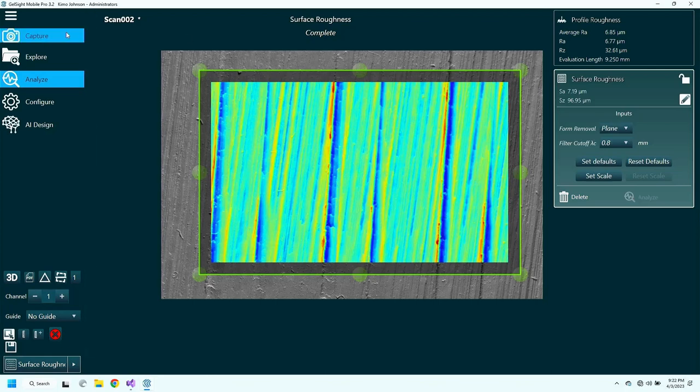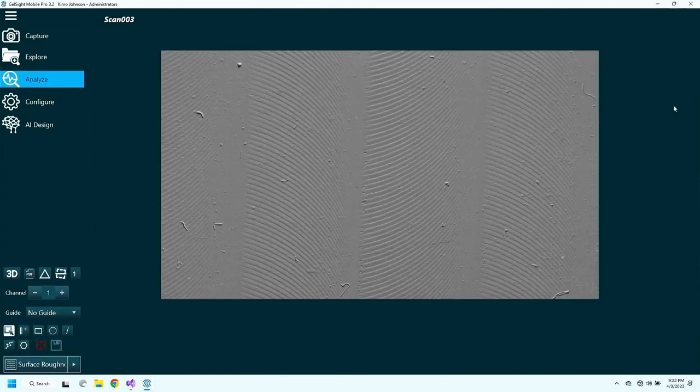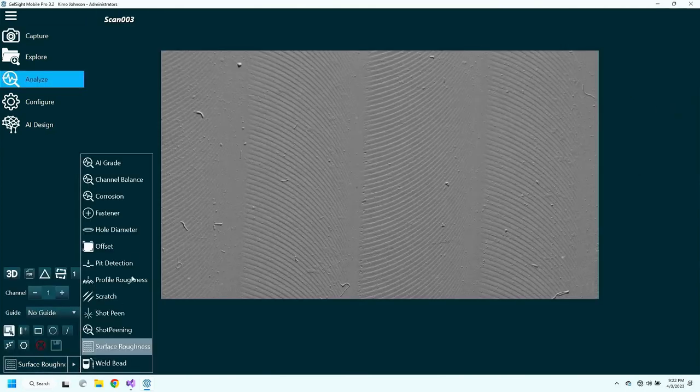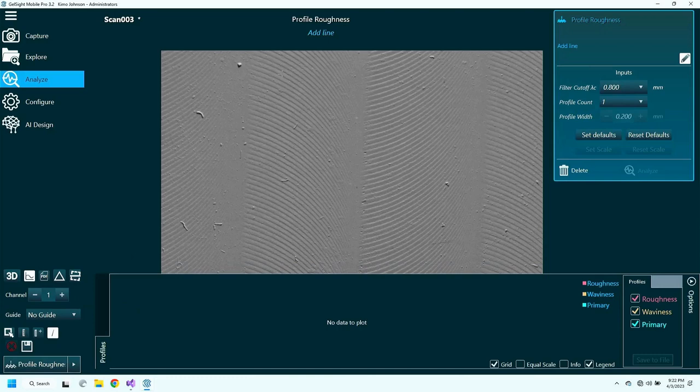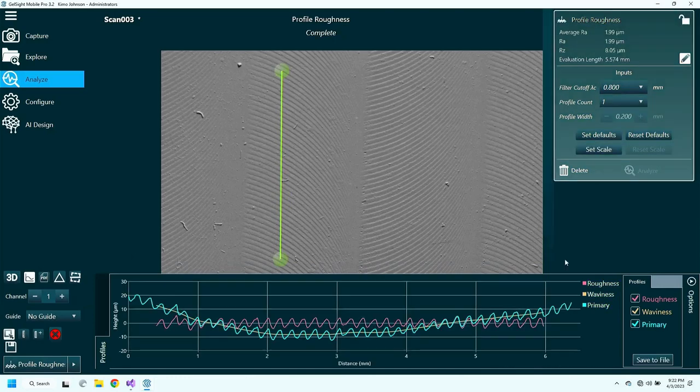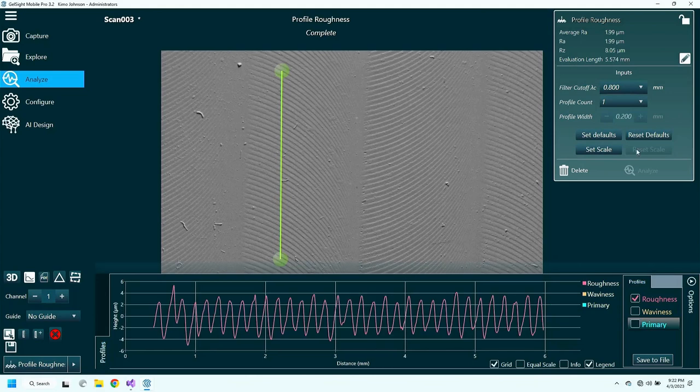Now, I had also measured this other part, which has different surface characteristics. So I'll do the same measurements in this part. Here we can see the roughness goes in a different orientation. So the natural orientation of this roughness is vertical. You can see it's a much smoother part with an average RA of about 2 microns.